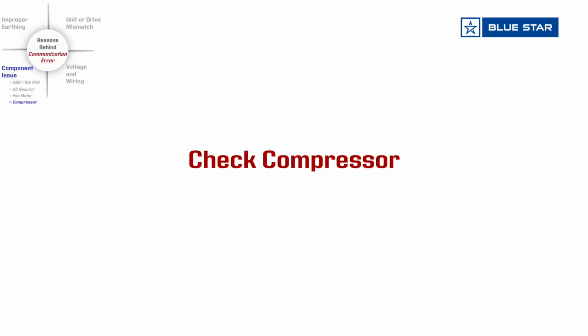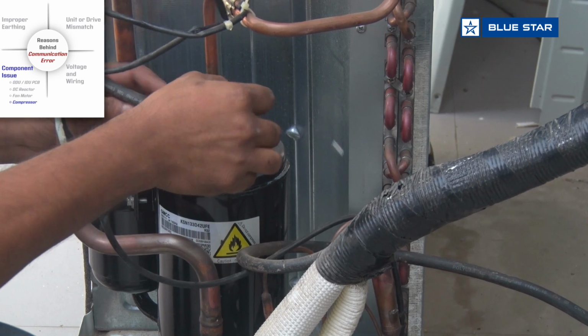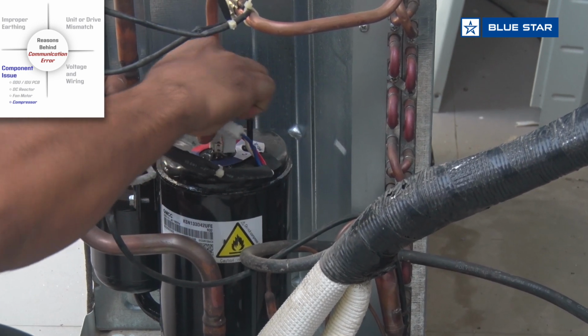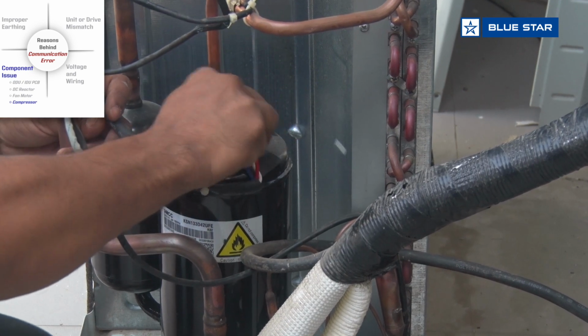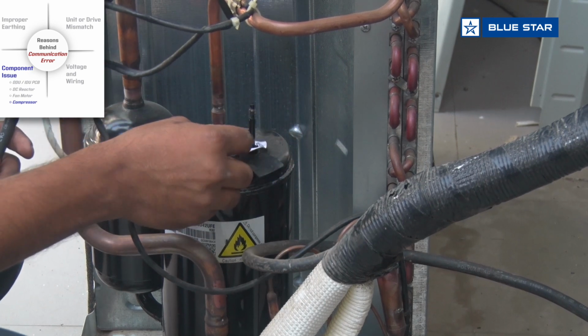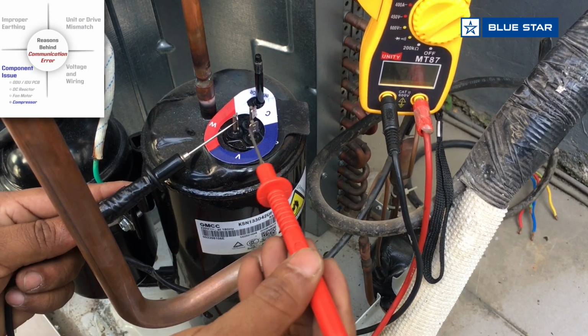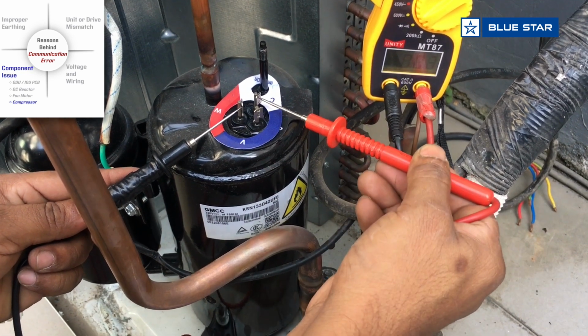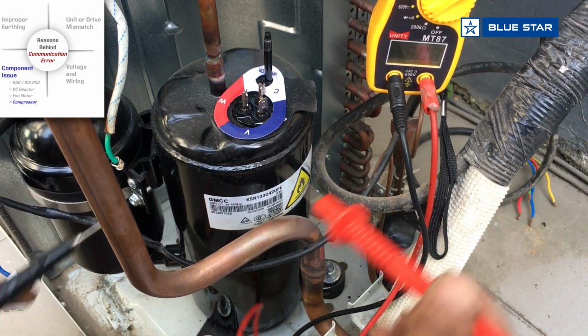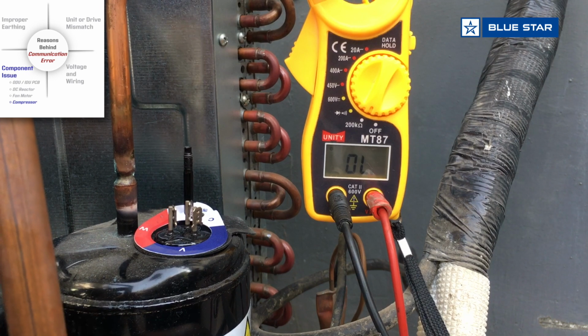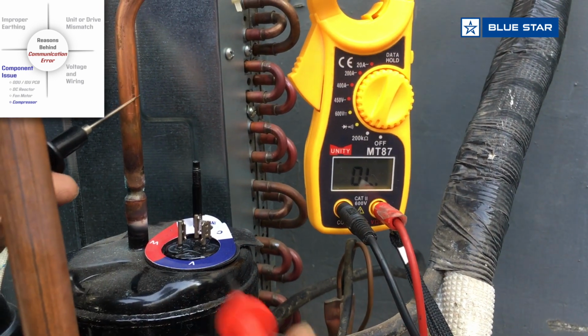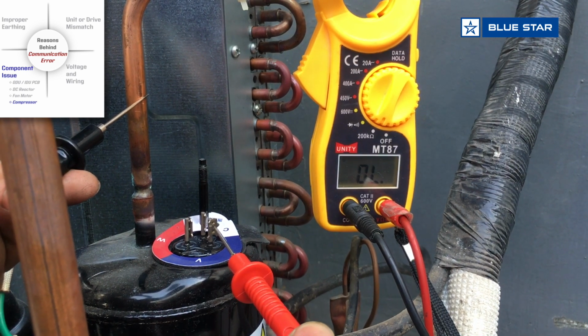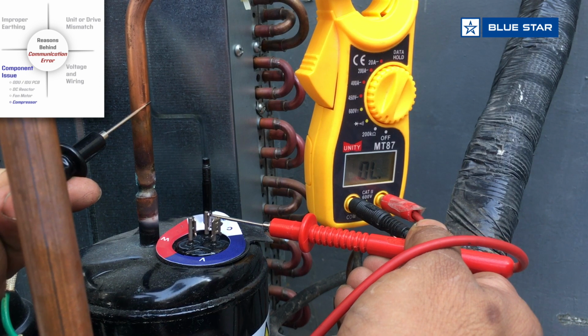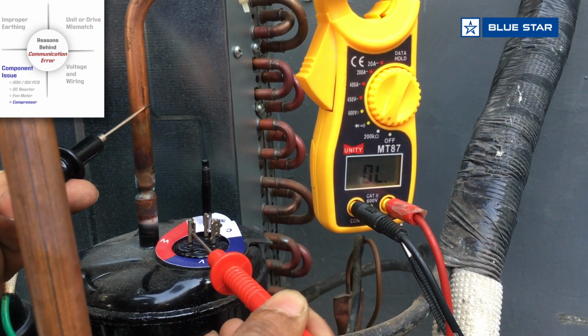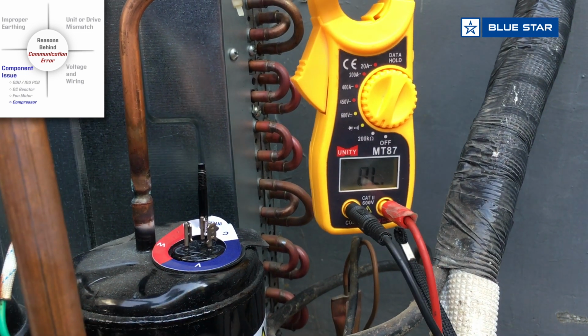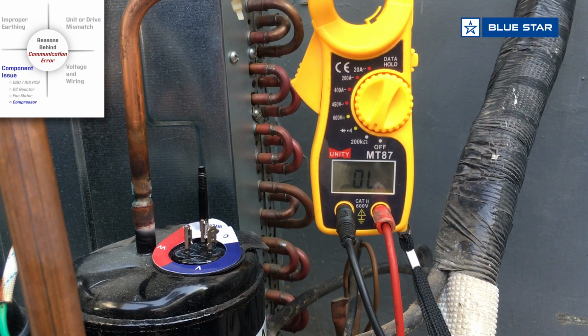Now it's time to check the compressor. Remove all the compressor connections and check the resistance across the 3 terminals. In a healthy condition, resistance between VW, WU and UV will be the same. Now check if the compressor is grounded by checking resistance between each compressor terminal and body. If the resistance shows OL, then it is healthy, else it is concluded that the compressor is faulty and has to be replaced. Please note, if the compressor is faulty, the replaced new ODU drive may get damaged, causing communication error.